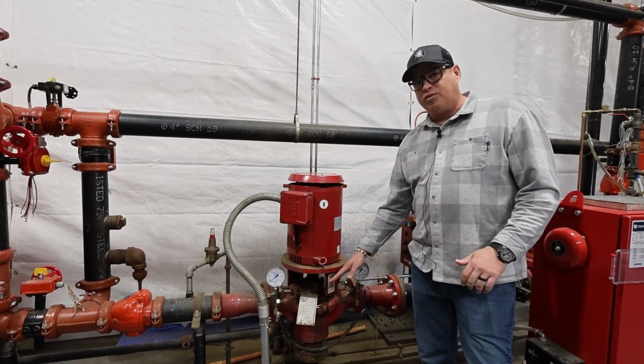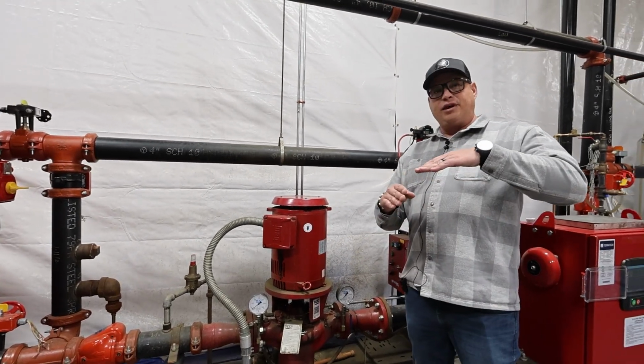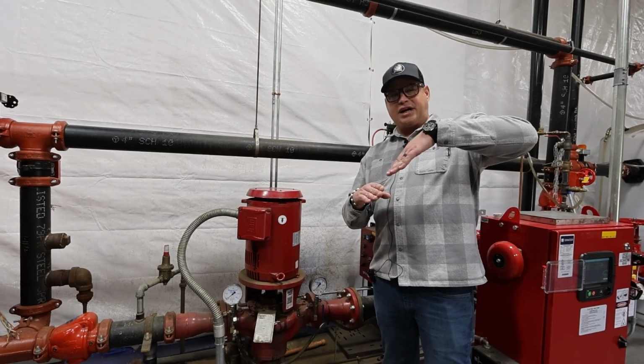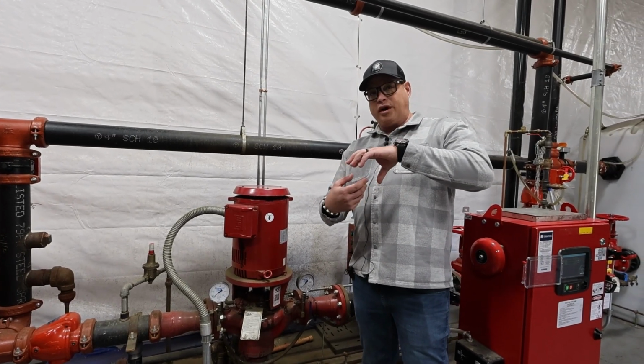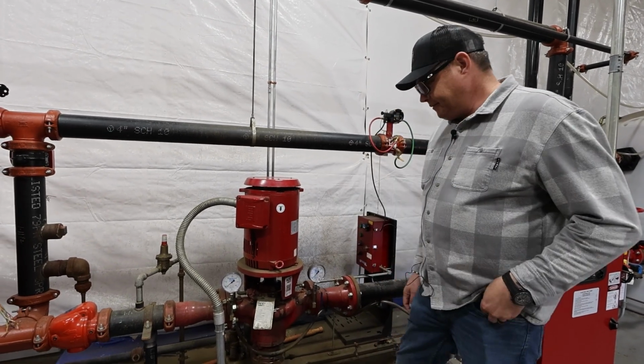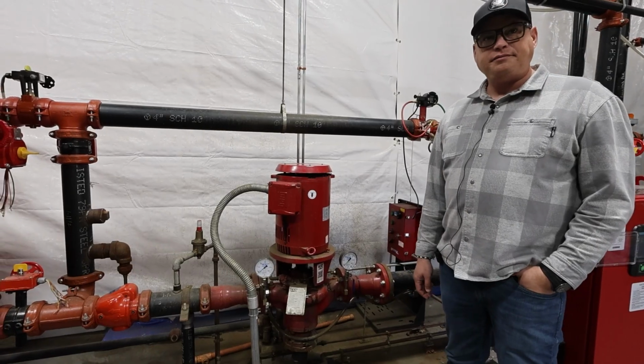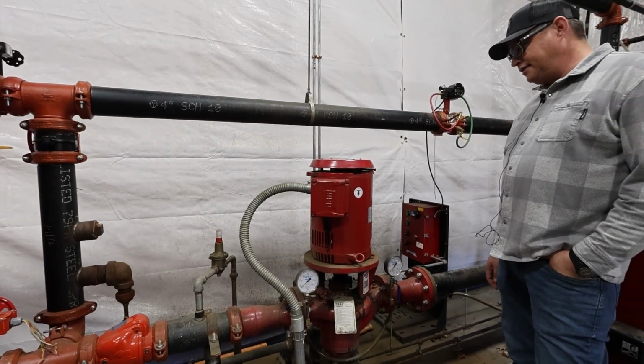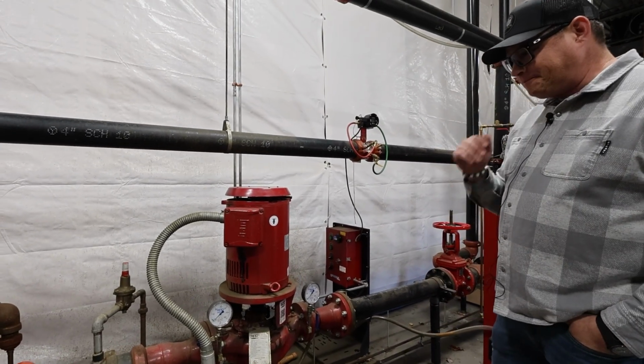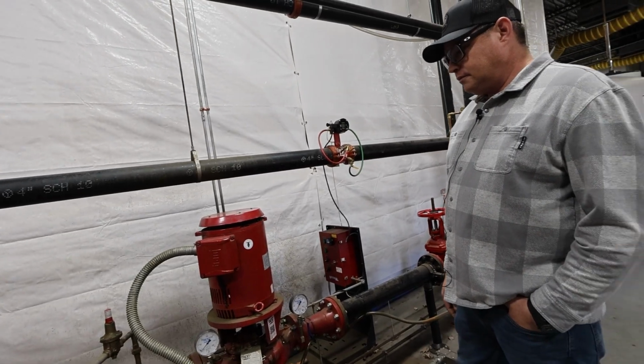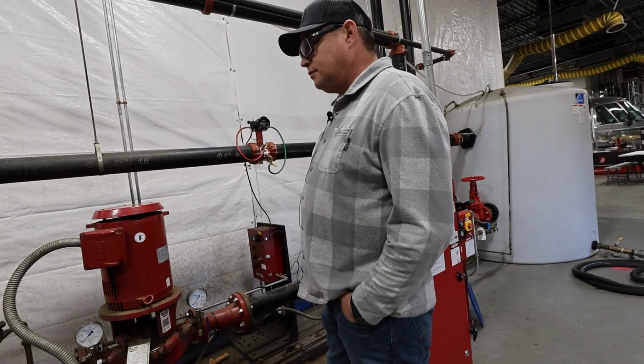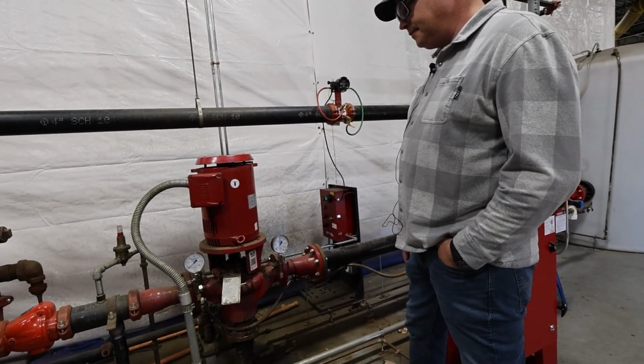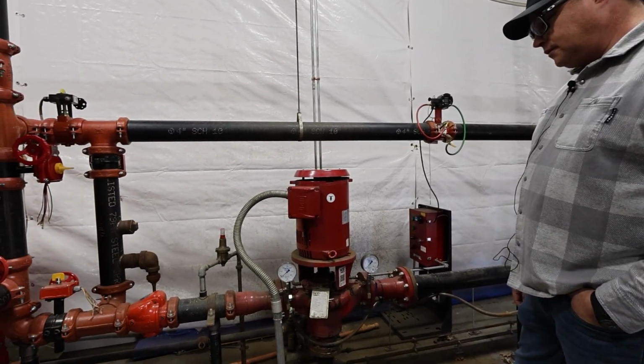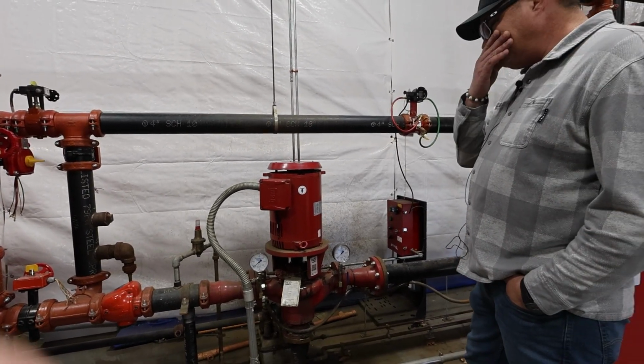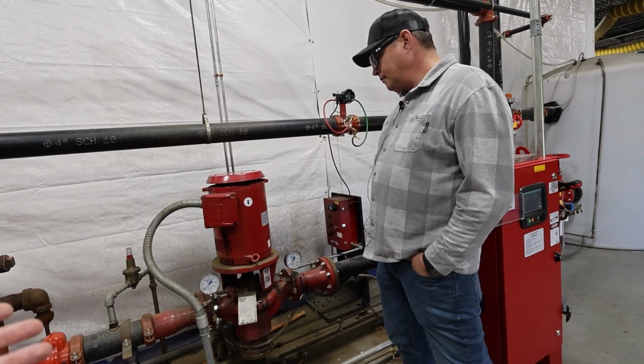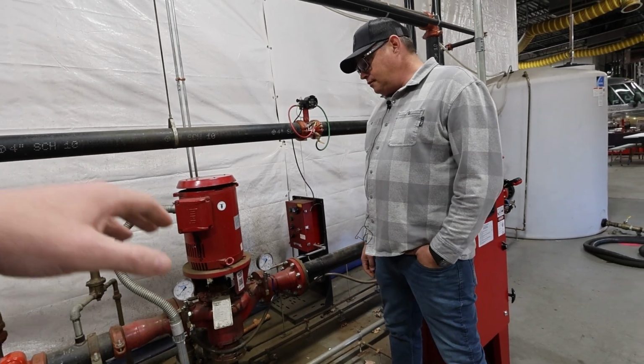If you go too hard on one side, the gland itself will actually cut into the shaft sleeve and could cause scoring, which would later break the shaft sleeve. You do that while the fire pump's running as well. Minor adjustments while the pump is running. Very minor adjustments, yes. Awesome. Yeah. So other things we're looking for, say we're running, the pump's not running right now, obviously it's quiet. But what are the other things that we're looking for on a vertical inline pump while we're running? The temperatures that you're talking about, are you taking bearing measurement temperatures? Are you taking the pump itself, the motor?